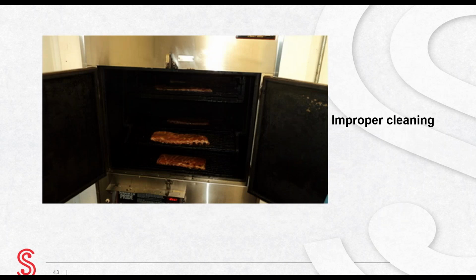You saw this picture previously in this presentation. The reason the doors and interior are difficult to see is because they are totally encased in grease. There is a large buildup of creosote and grease throughout the unit. This is a fire hazard that we have been talking about. In addition, the meat smoker passes through an exterior combustible wooden wall.